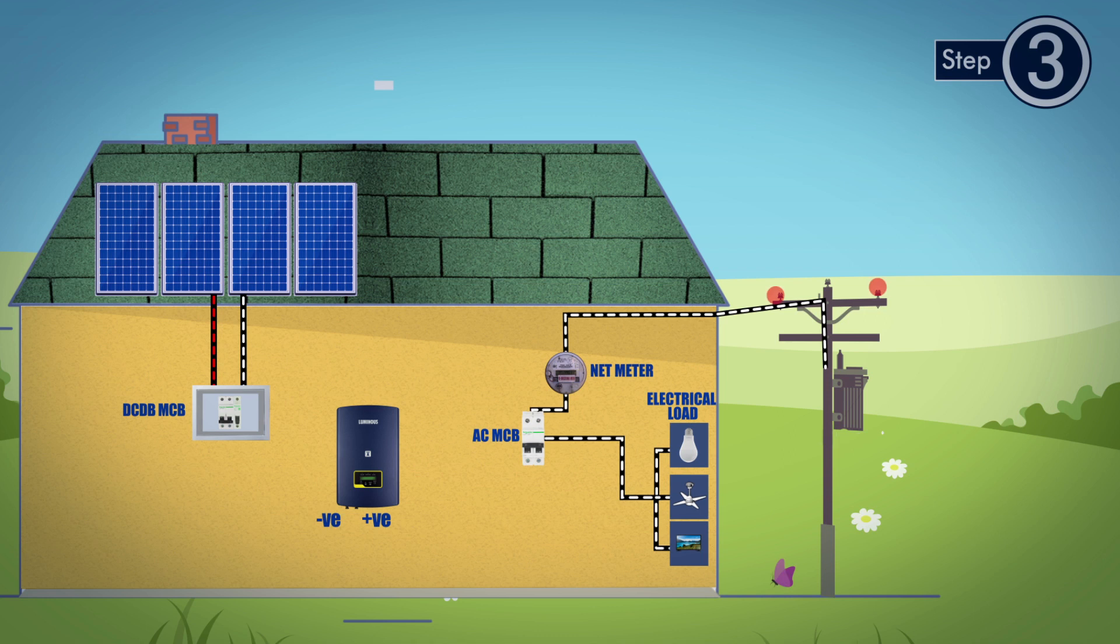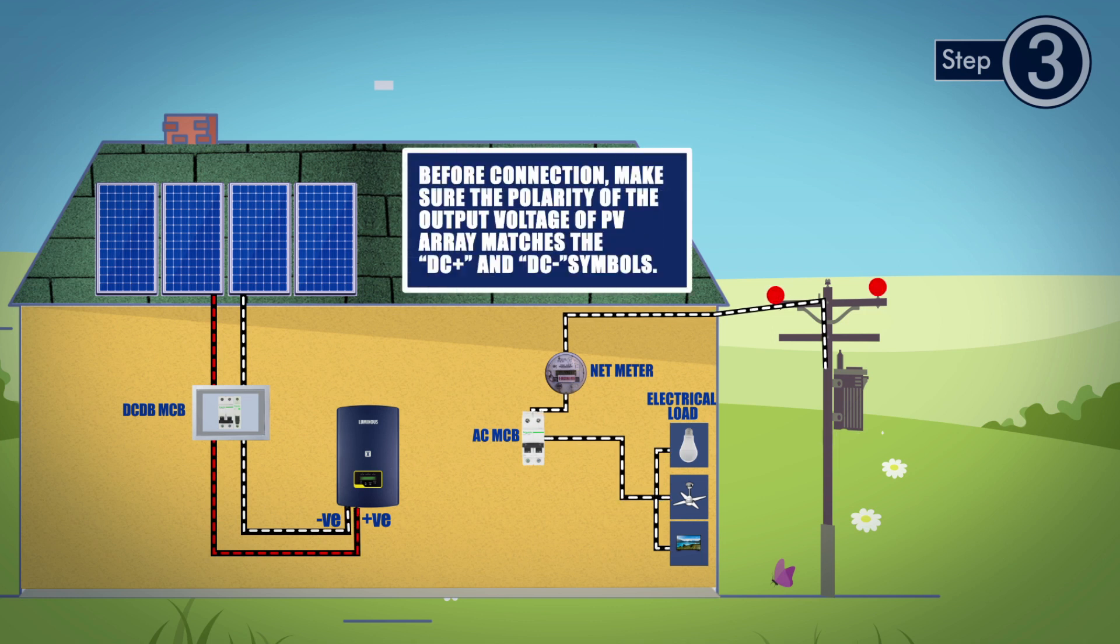Take the output from the DC MCB to the positive and negative terminals of the DC1 on the inverter. Before connection, make sure the polarity of the output voltage of PV array matches the DC positive and DC negative symbols.